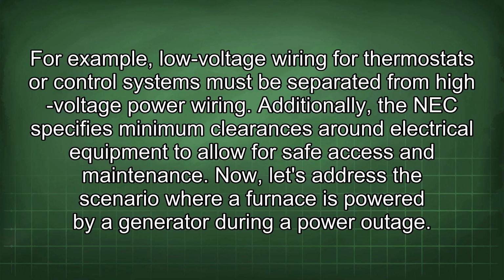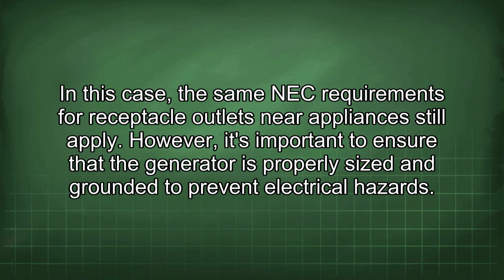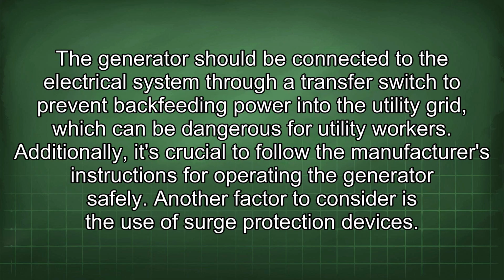Now, let's address the scenario where a furnace is powered by a generator during a power outage. In this case, the same NEC requirements for receptacle outlets near appliances still apply. However, it's important to ensure that the generator is properly sized and grounded to prevent electrical hazards. The generator should be connected to the electrical system through a transfer switch to prevent backfeeding power into the utility grid, which can be dangerous for utility workers. Additionally, it's crucial to follow the manufacturer's instructions for operating the generator safely.